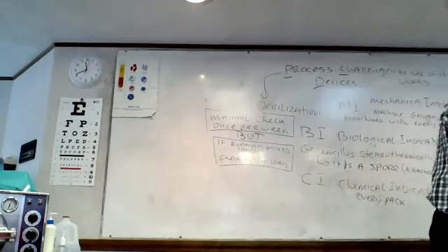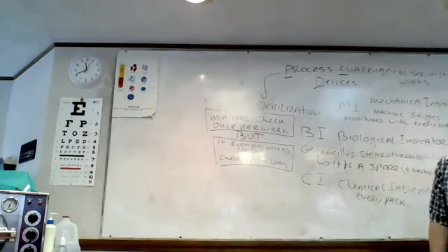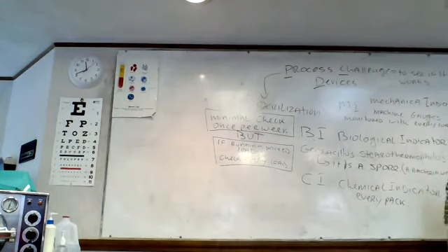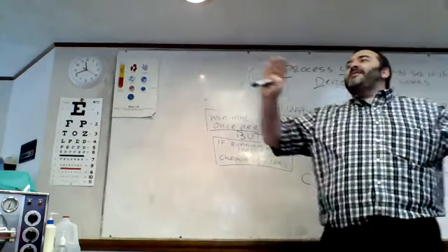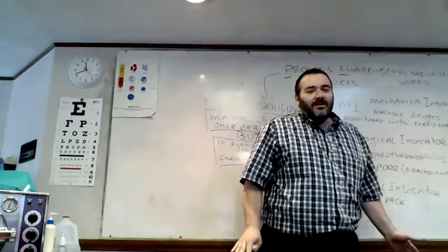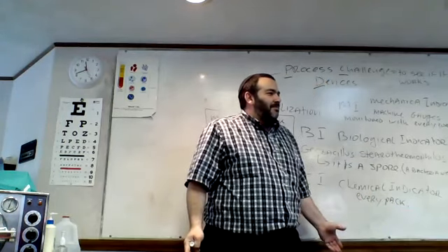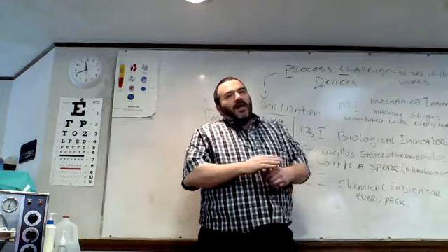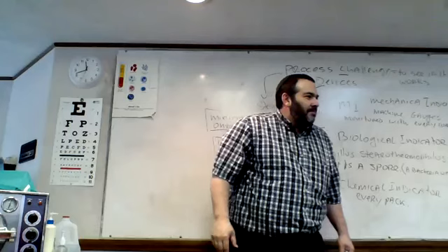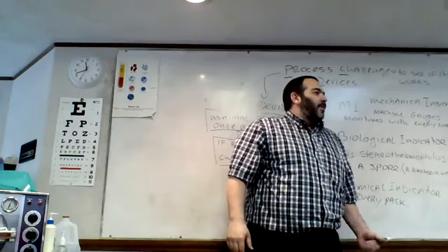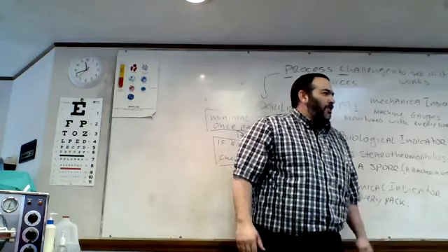What is the minimum, the minimal value, once a week for biological indicator? What's a mixed load? I'll explain. If I'm sterilizing nothing but stainless surgical steel, it's not a mixed load. However, if I want to throw in an implantable device and I want to sterilize that, what did I just do? I mixed the load.